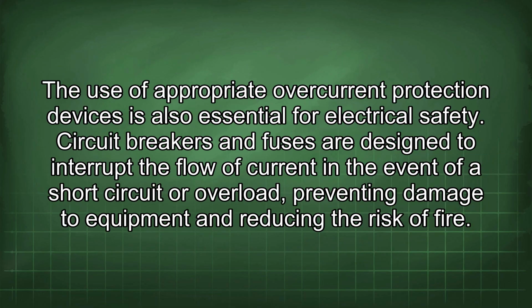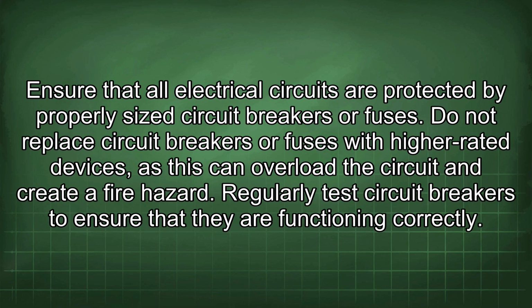The use of appropriate overcurrent protection devices is also essential for electrical safety. Circuit breakers and fuses are designed to interrupt the flow of current in the event of a short circuit or overload, preventing damage to equipment and reducing the risk of fire. Ensure that all electrical circuits are protected by properly sized circuit breakers or fuses. Do not replace circuit breakers or fuses with high-rated devices, as this can overload the circuit and create a fire hazard. Regularly test circuit breakers to ensure that they are functioning correctly.